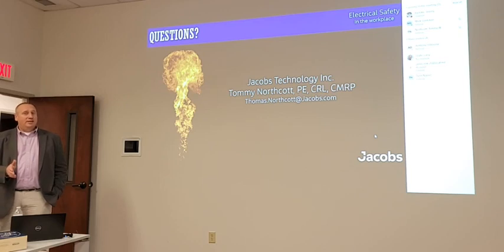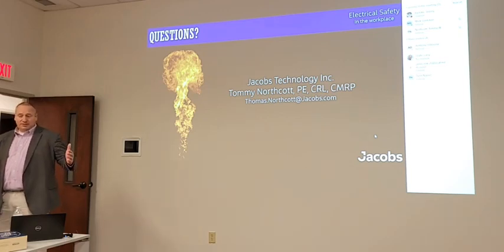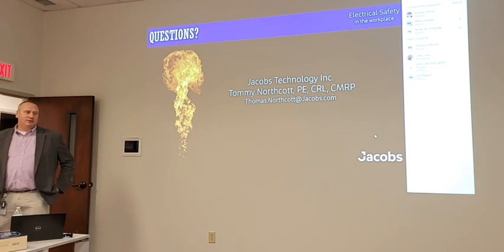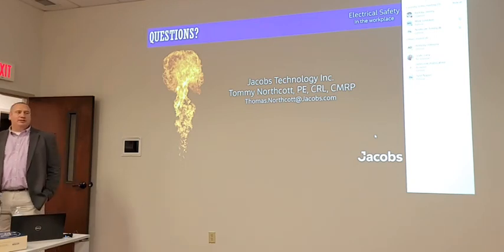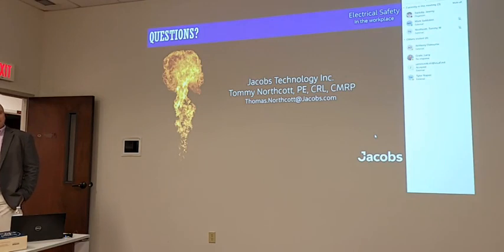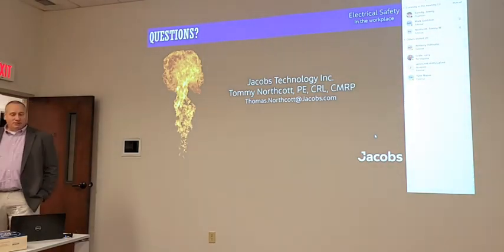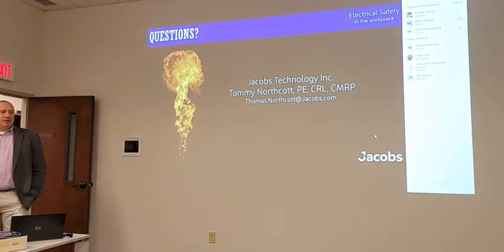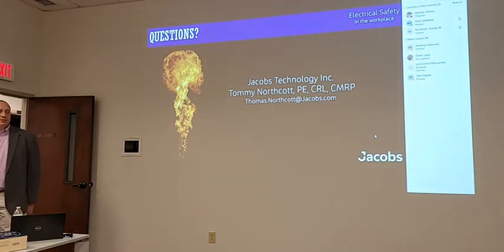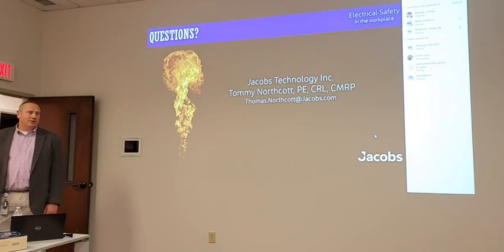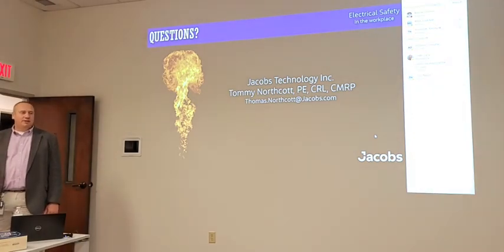But that being said, if there's a scenario where you've got this gear that's automated and it's going to be coming on and off, and we're going to be spending 4 hours today in front of it, then to do that 4-hour task, maybe we need to find a window where we can de-energize all those controls, where they're not coming on and off when we're in that area. So that's where the risk assessment really comes in to evaluate what we are doing. Are we just walking by the gear? That's not a problem. Are we setting up for a week in front of this gear? Well, then maybe we need to take some extra precautions to keep it from automatically operating. That makes sense.